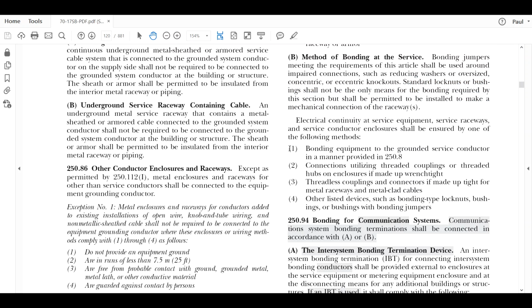All right, now what are our options? Well, remember, I can't use 1 to do that bonding, but I can use 2, 3, and 4. So again, we're not using any exceptions in 250.92. We're just using these. It says connections utilizing threaded couplings or threaded hubs on enclosures if made up wrench tight. Well, that's not really an issue in ours because we're not talking about hubs or Myers hubs. So that really is not going to come into play for us. The next would be threadless couplings and connectors if made up tight for metal raceways and metal clad cables. So that's probably what we would use. There probably would be threadless couplings or connectors. They're just simply more of a compression type, and that would be fine.